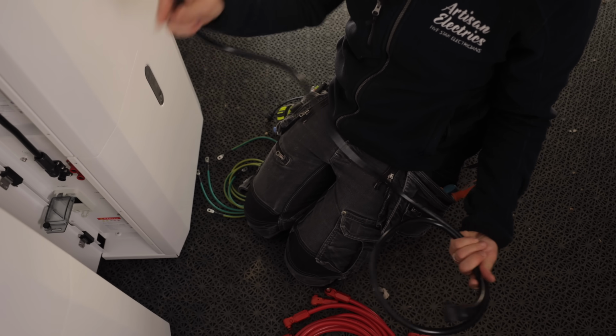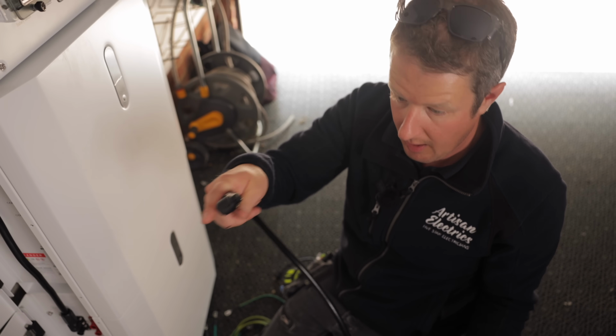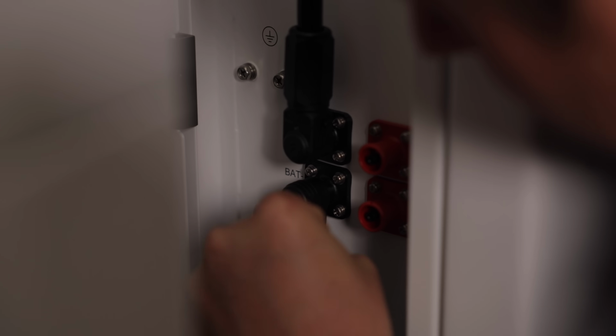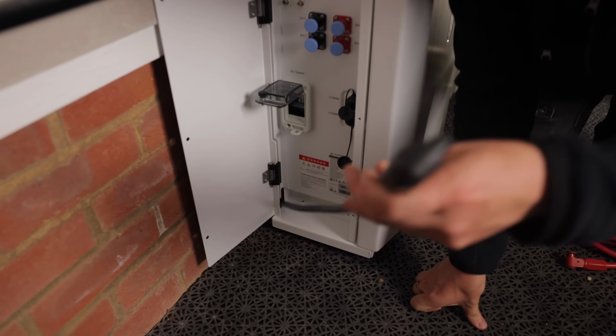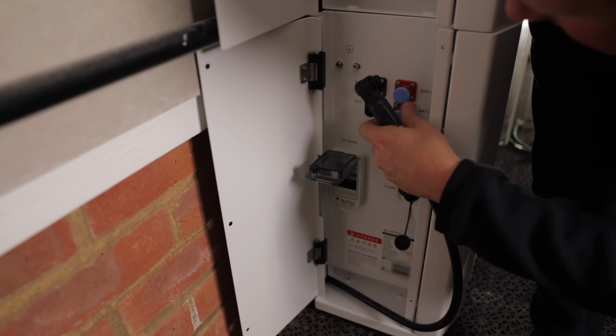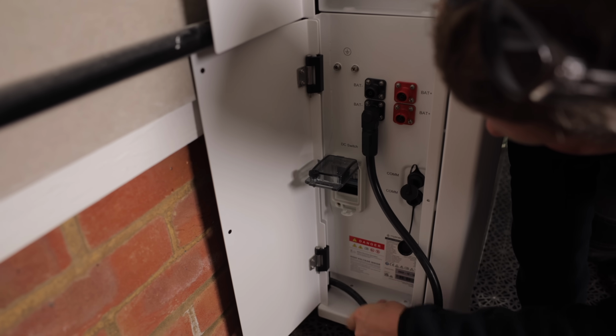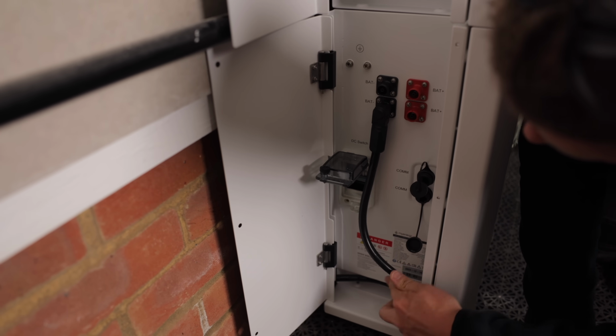The long negative cable goes from this bottom battery across and up. We've got to thread it through this little hole in the side of the door, bearing in mind that hole also needs two reds coming through and an earth wire, so quite a lot of cables go through there. We'll slide it through gently until the length is correct, click that one in, keep sliding it through, and pull it on the other side. On the second stack we'll pull the extra slack through, and that goes into this battery negative here. There's a little bit of slack, but not a lot, which is why I said earlier to space them 600 apart - there's just no way the cables would reach.